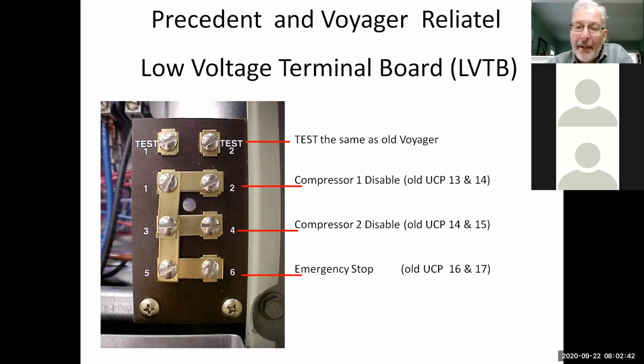If you stop at any given point, so say I get to, you know, step 3, I've got the compressor running. If I take the jumper off, it'll stay there for 1 hour. Okay, so that gives you time to do some diagnostics and look at different things. So anytime you take the jumper off at any given point, it'll stay there for 1 hour, and after an hour, it just goes back to normal operation.